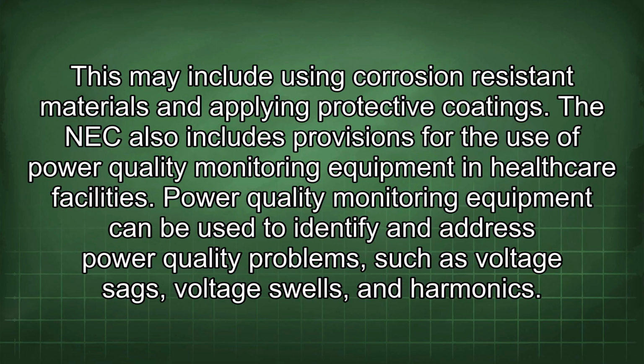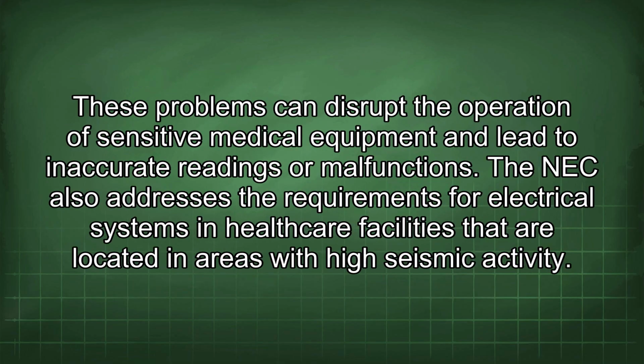The NEC also includes provisions for the use of power quality monitoring equipment in healthcare facilities. Power quality monitoring equipment can be used to identify and address power quality problems such as voltage sags, voltage swells, and harmonics. These problems can disrupt the operation of sensitive medical equipment and lead to inaccurate readings or malfunctions.